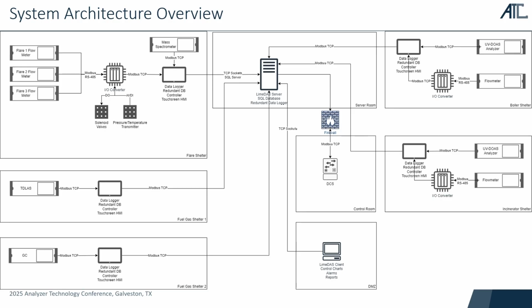So we're not reducing measured data, which we collect with around 10-second interval, depending on the instrument. GC would be a little longer. We're storing all the raw data, all the raw alarms, and then in real time, as we need to trend data or generate a regulatory compliance report, we recursively build that out. So from measured value, we build 1-minute averages, we build validated 15-minute averages. From that, we validate 1-hour averages, and then we have all the custom rules for the regulations I mentioned earlier, like rolling 3-hour average, 7-day average, and even 365-day, 1-year average. And with that method, if we're talking about redundancy, whenever the data is synced over, it's automatically processed. So there's no need to do any additional maintenance or reviewing the data and trying to match how the data works together.